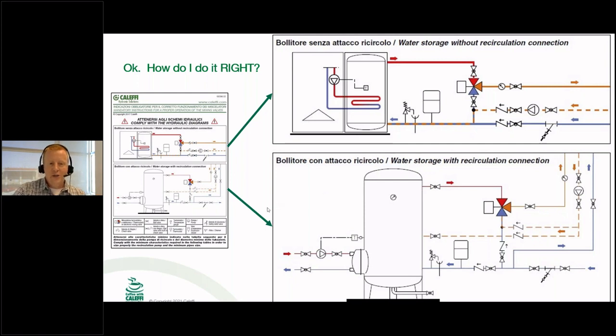Now, our Legiomix here, we actually take this diagram and we help you to learn Italian because it's bilingual here, but we also zip tie this to every single Legiomix valve body. And it's got two different piping diagrams on there. One for a smaller domestic hot water system without a recirc connection on the tank, and then one with a recirc connection on the tank.